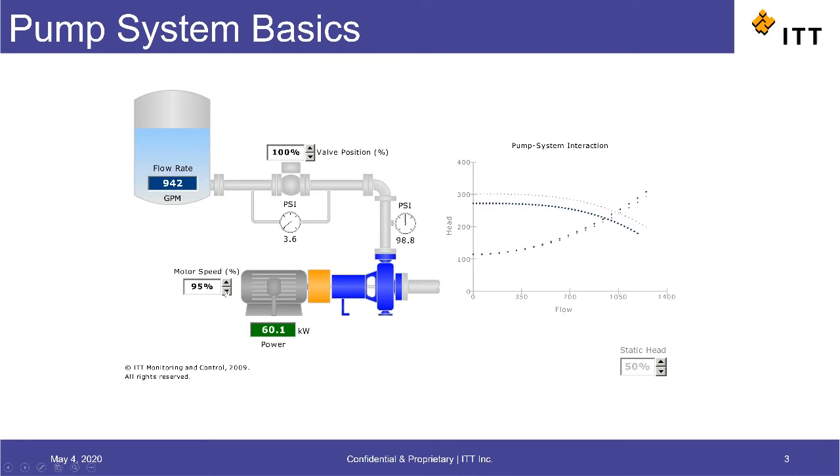So what happens is we leave the system curve in its original shape with the discharge valve fully open. And as the motor speed and therefore the pump speed come down, we're shifting the pump curve down until it intersects with the system curve close to our desired flow rate.